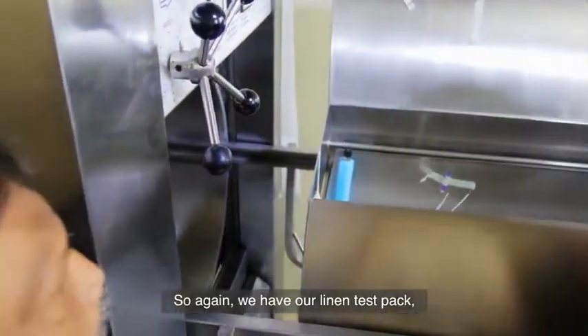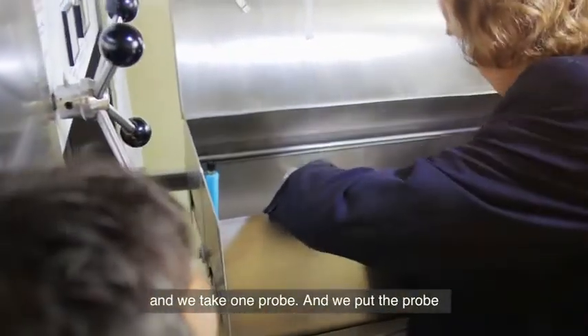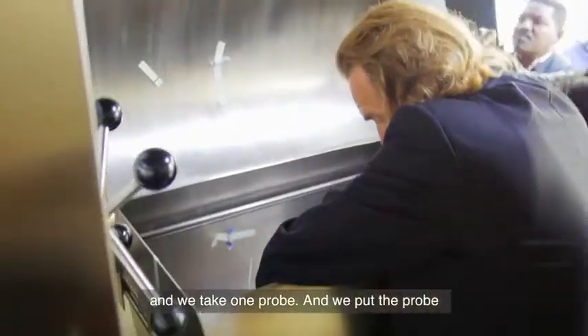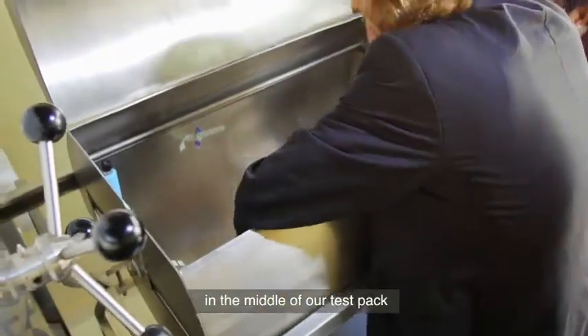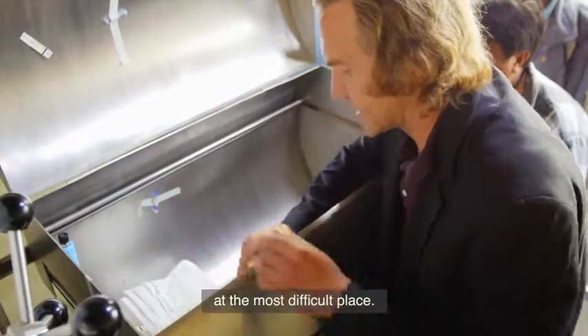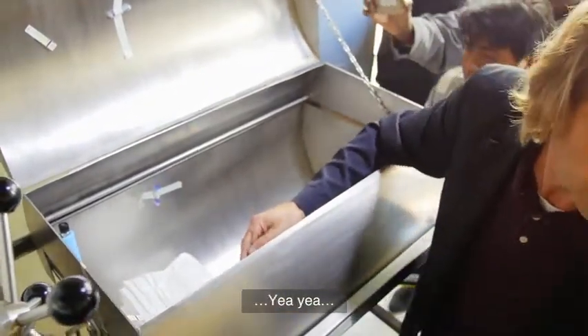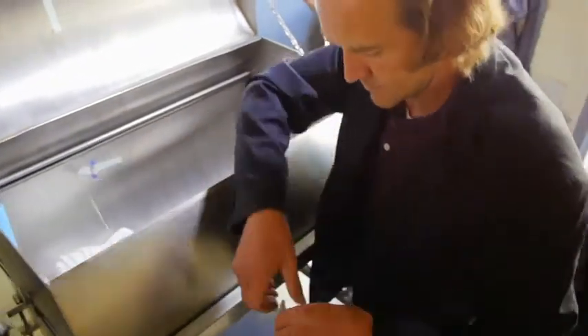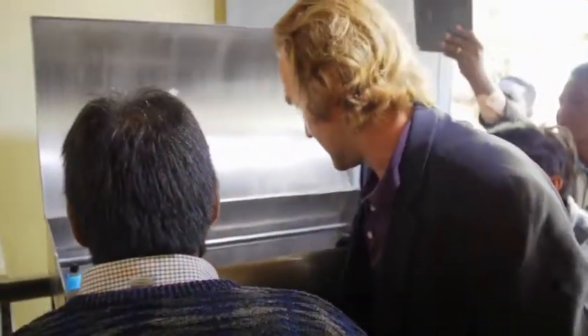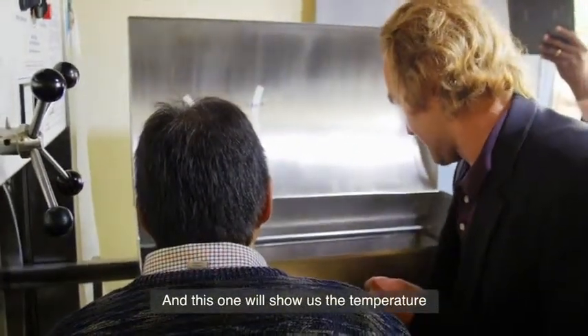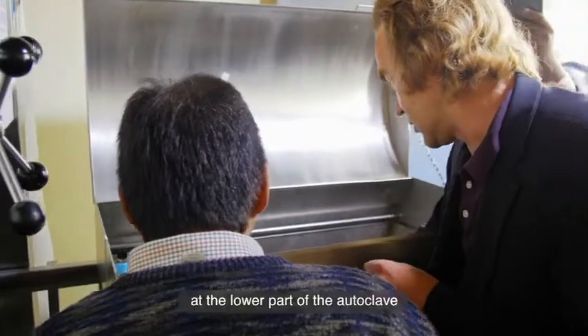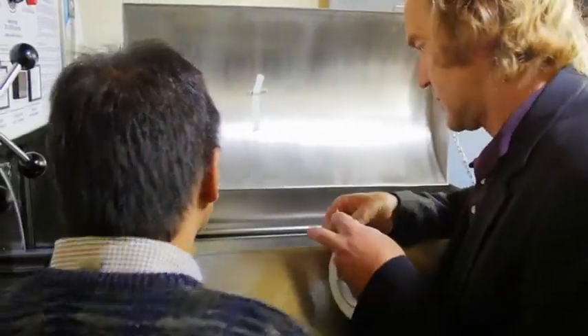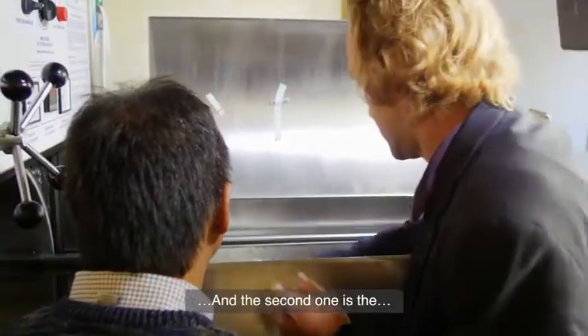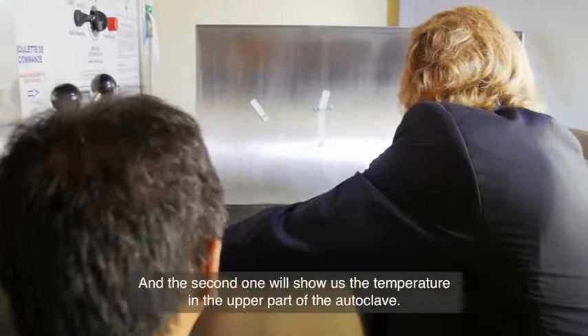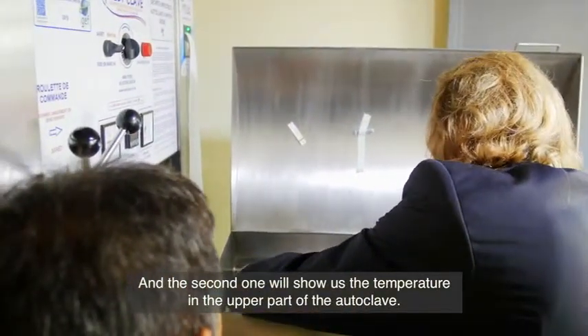So again, we have our linen test pack, and we take 1 probe and we put the probe in the middle of our test pack at the most difficult place. And then we can take 1 probe. You have some autoclave tape? Some tape. And this one will show us the temperature at the lower part of the autoclave. And the second one then will show us the temperature on the upper part of the autoclave.